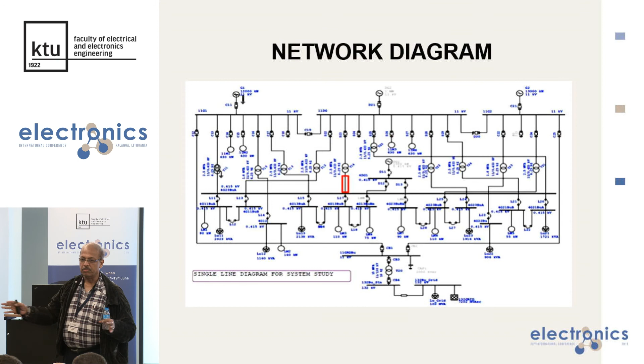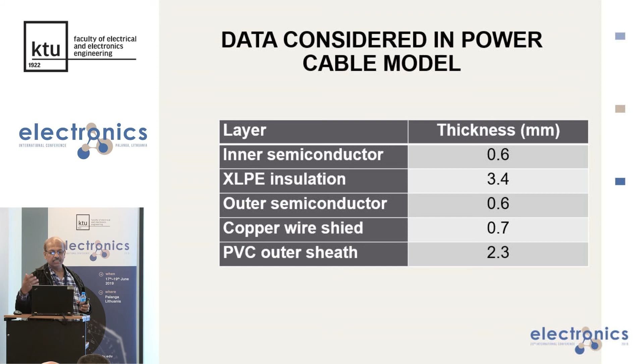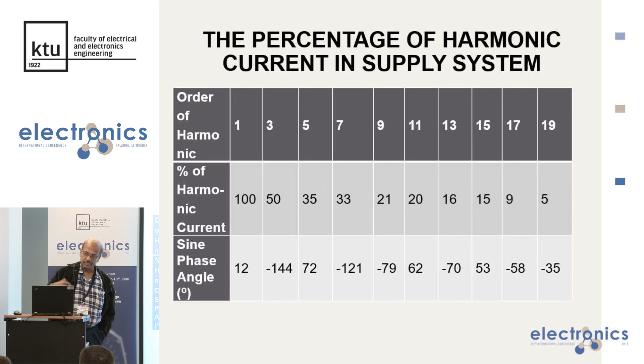The data considered in the cable model are available from the world manufacturer of this cable, and there we have collected the thickness and the design cable data, and the percentage of harmonic current in the supply system. Here you see that for the first order it is 100% current, and for the third harmonic portion it is 50% harmonic current. This is the distribution, and up to the ninth harmonic the maximum loss generation is there.